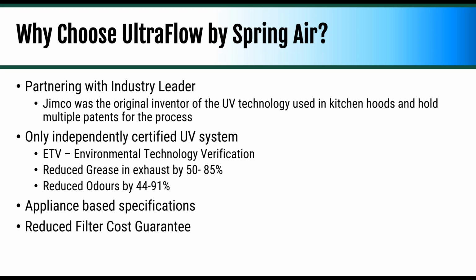I don't know if anyone here is familiar with the SpringAir approach. We always start with appliances, as I mentioned before. None of the other manufacturers that use UV use anything other than one standard frame size, which I say frame, but essentially it's the number of bulbs and the wattage of the bulbs in the hood, so they just do it based on linear feet of hood. We're doing it in concert with guidance from Jimco based on appliances. So if you've got a charbroiler, we're putting in way more bulbs and way higher wattage than if you've just got ovens or tilt skillets, things like that.